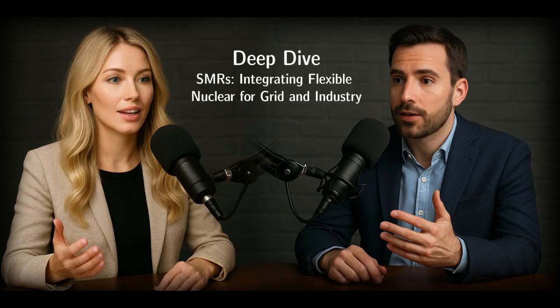Oh, absolutely. It demands sophisticated protection schemes. Think differential protection for the generator, the transformer, the transmission lines, often needing high-speed communication between relays for proper coordination. And careful coordination with existing transmission protection is key, plus robust backup systems like distance and overcurrent protection. You need to detect and isolate faults instantly.